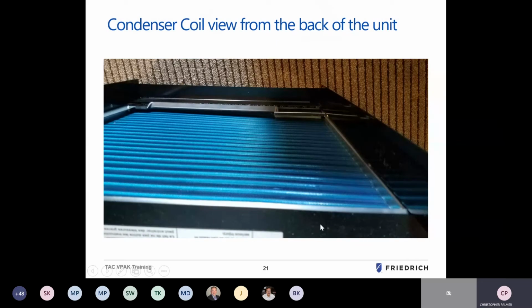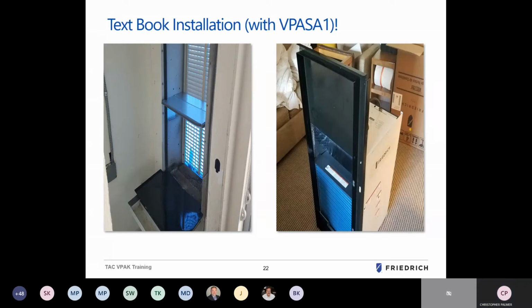This is a view of the back of the unit that shows our Blue Diamond coating on our coils, which is our seacoast protection. This also shows the back side of the image with our First Company sleeve adapter, which is available in our 09 and 12 model units. Which leads us into the pictures above. Textbook installation with the VPA SA1. As you can see here, this is the VTAC with the First Company sleeve adapter, and then this is the platform. This is where an existing First Company unit was removed. The sleeve was modified with our modification kit. This is the bottom pan block-off piece, and this is the baffle extender in the appropriate position. And now this unit will be installed in the existing sleeve. The adapter will tie right into that previous First Company sleeve, and we'll have a successful installation.